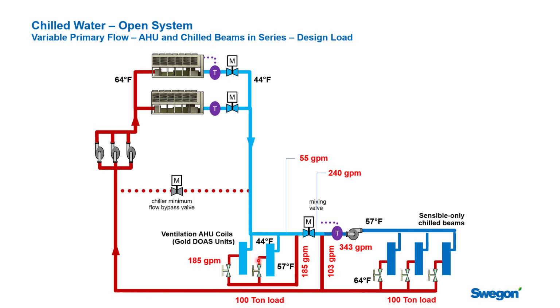Once the outside air temperature gets to the dew point of the supply air condition, there won't be any chilled water flowing through here. And all the water you need will come down through here and be mixed in here. And at that point, you can start talking about resetting the supply air temperature to do it. Or, as we will talk about in another video, you can start looking at waterside free cooling. Now, I've shown you how it's supposed to work. Let me break it for you so you appreciate what would happen if things go the wrong way. And to do that, I'm going to switch the loads. I'm going to leave this at 100 tons, but I'm going to drop this load to 50 tons.